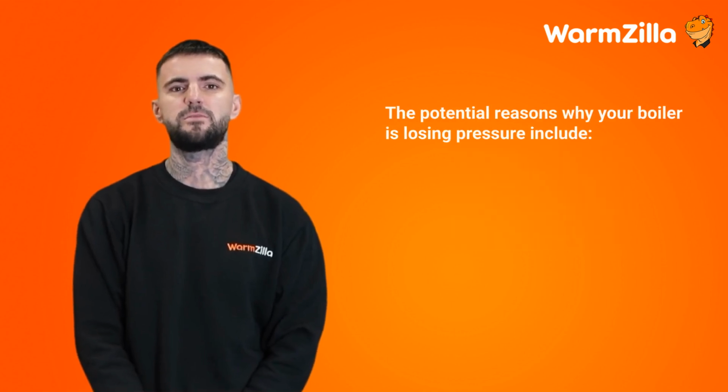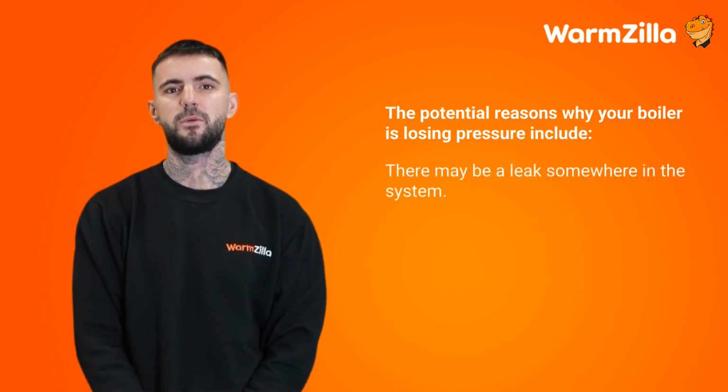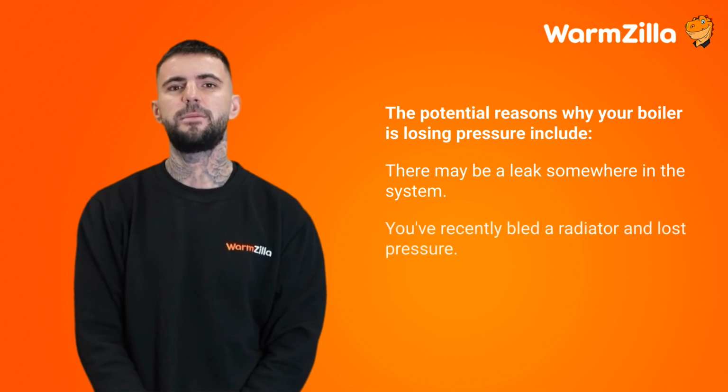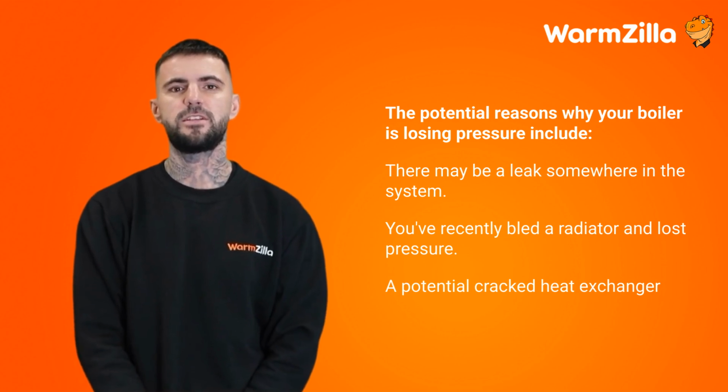The potential reasons why your boiler is losing pressure include: there may be a leak somewhere in the system. You've recently bled a radiator and lost pressure. A potential cracked heat exchanger. Make sure to address why your boiler's system is losing pressure before you reset it.